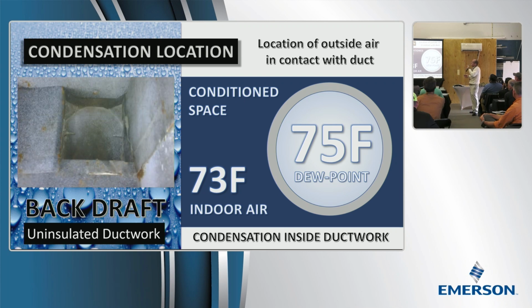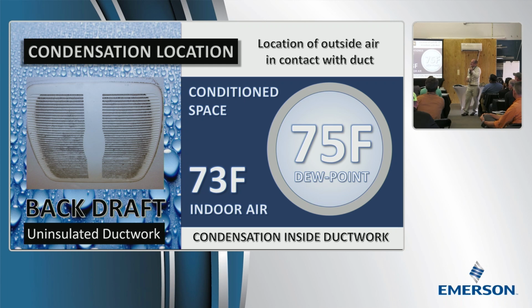Check your flappers. If you see moisture or evidence of moisture on a bath fan, it shouldn't have come from the room. If you were leaking dry air out, it wouldn't look like that. The reason it looks like that is that's moisture, 120 grains coming from outside, and the first condensing surface it hits is the bath fan. Whenever you see a bath fan rust out, why did it rust out? Because the flapper didn't work. The moist air hit the cold surface and you rusted out your bath fan. Otherwise, a bath fan shouldn't rust out if it's at the same dew point as the ceiling.